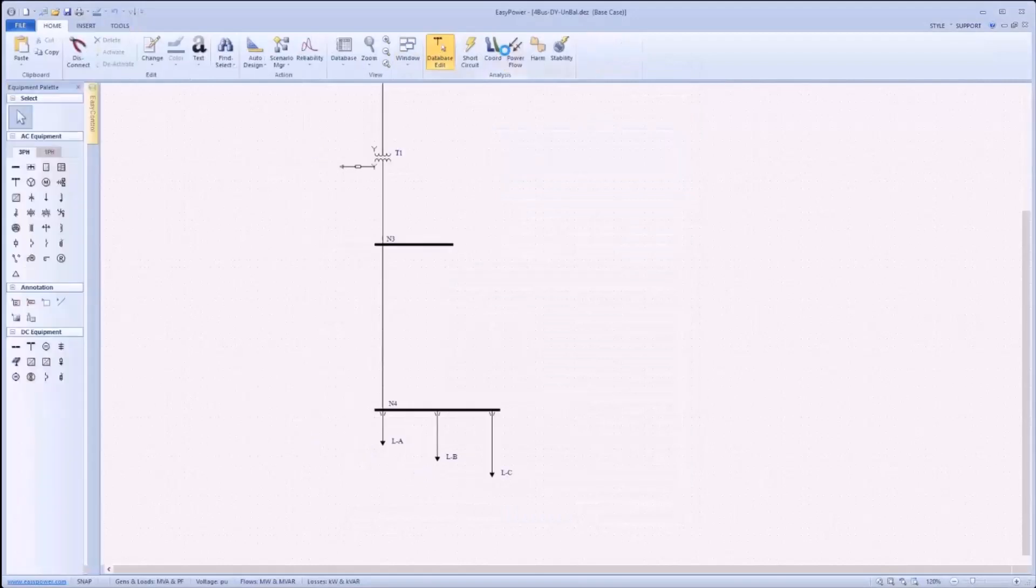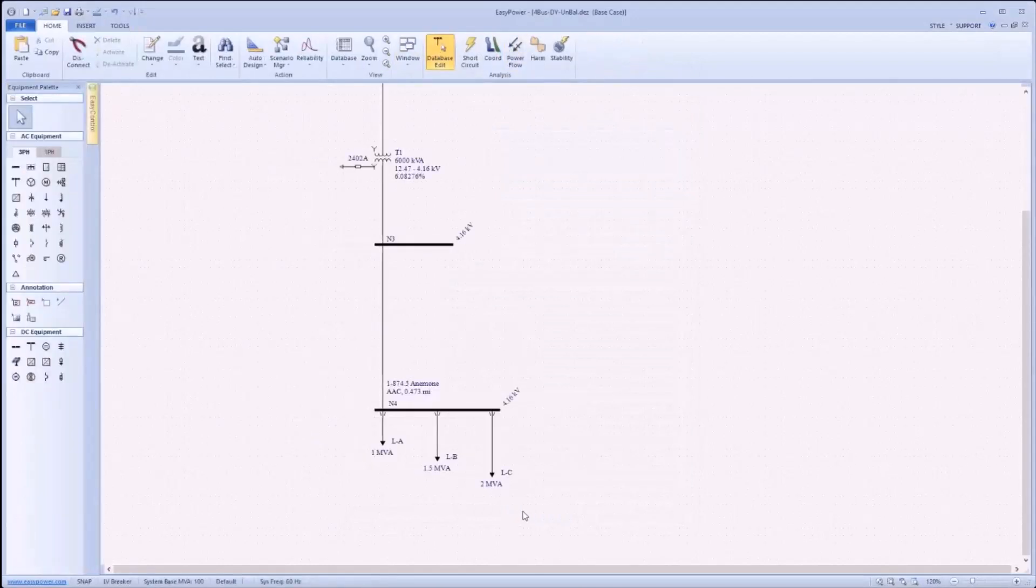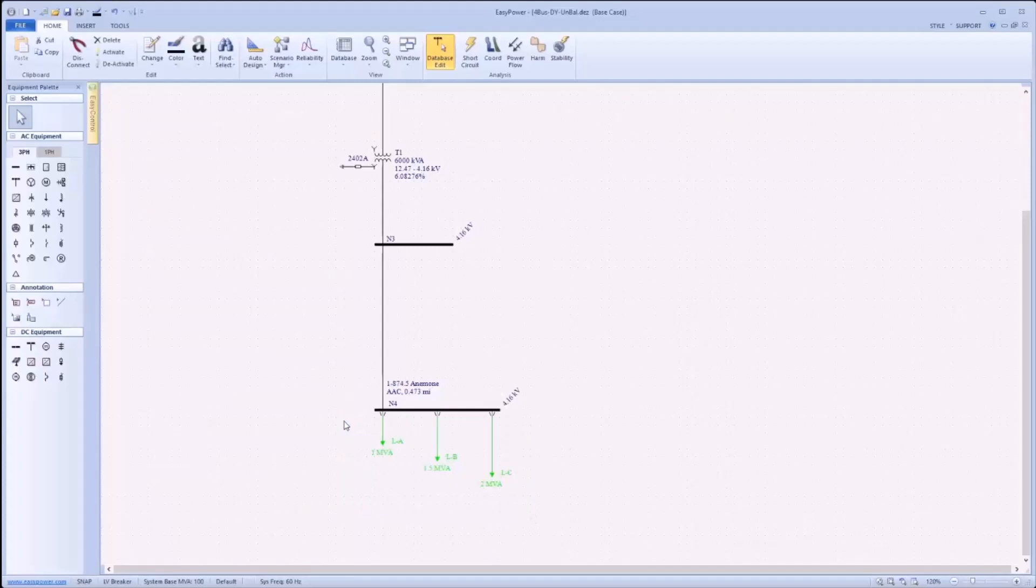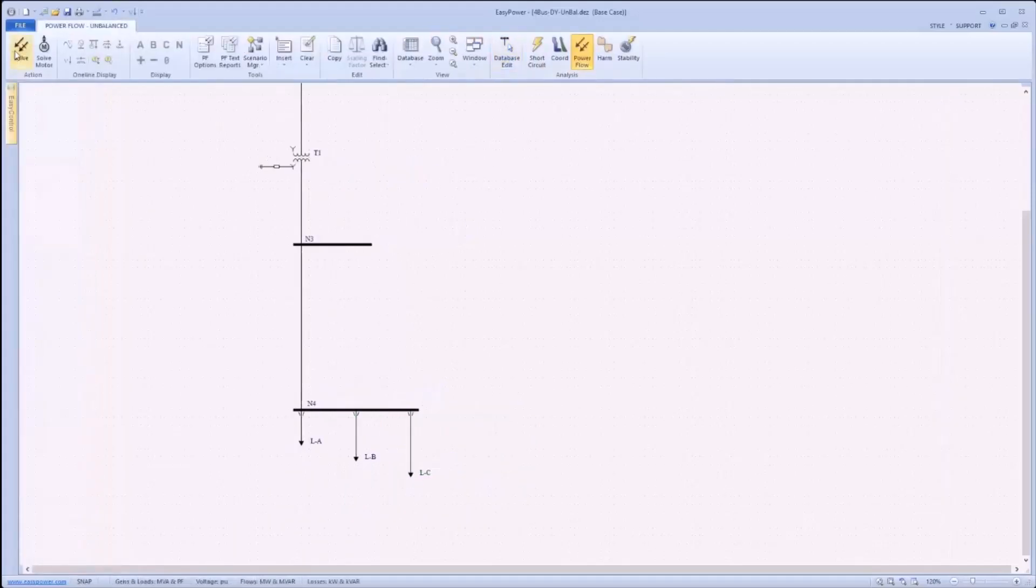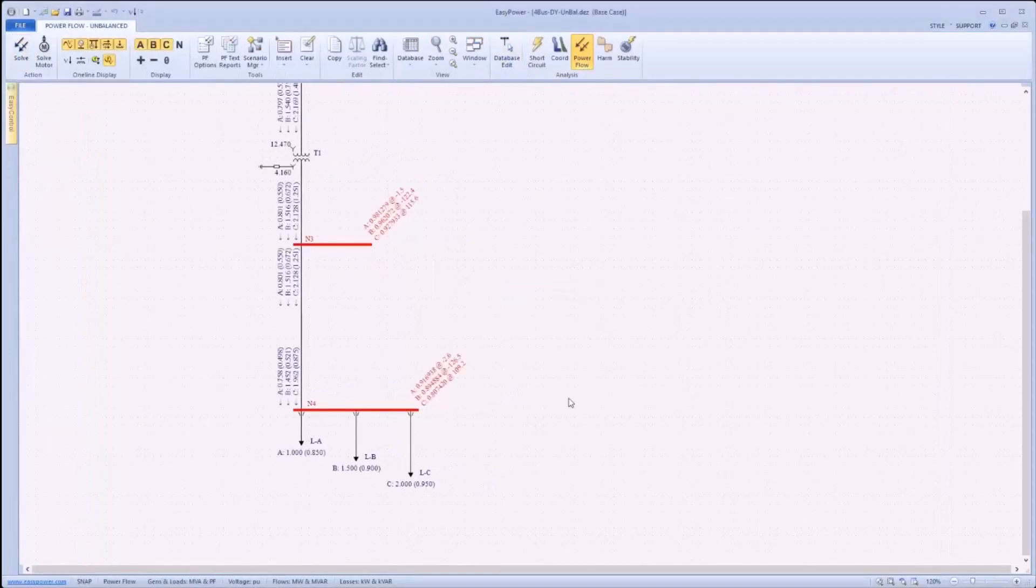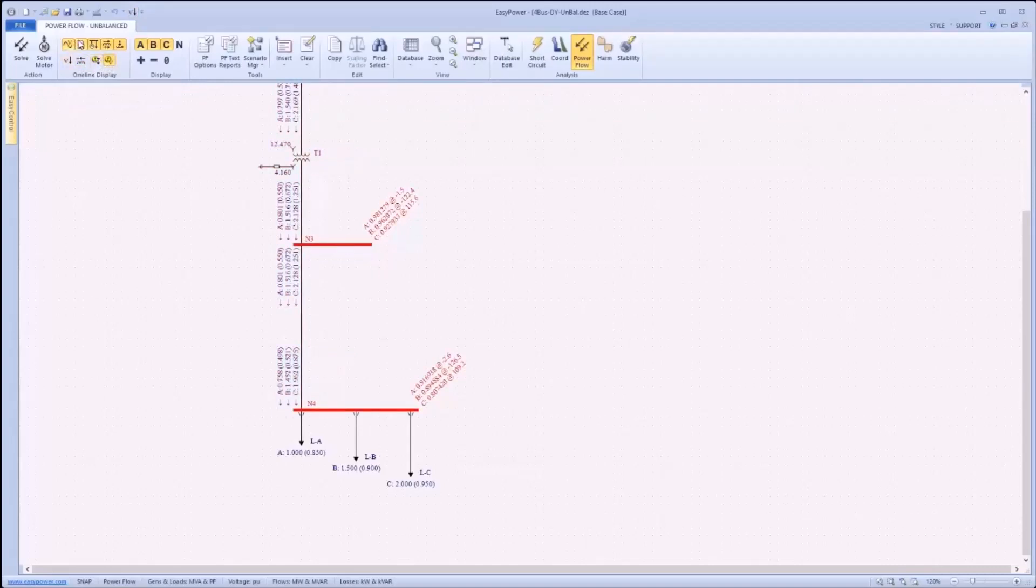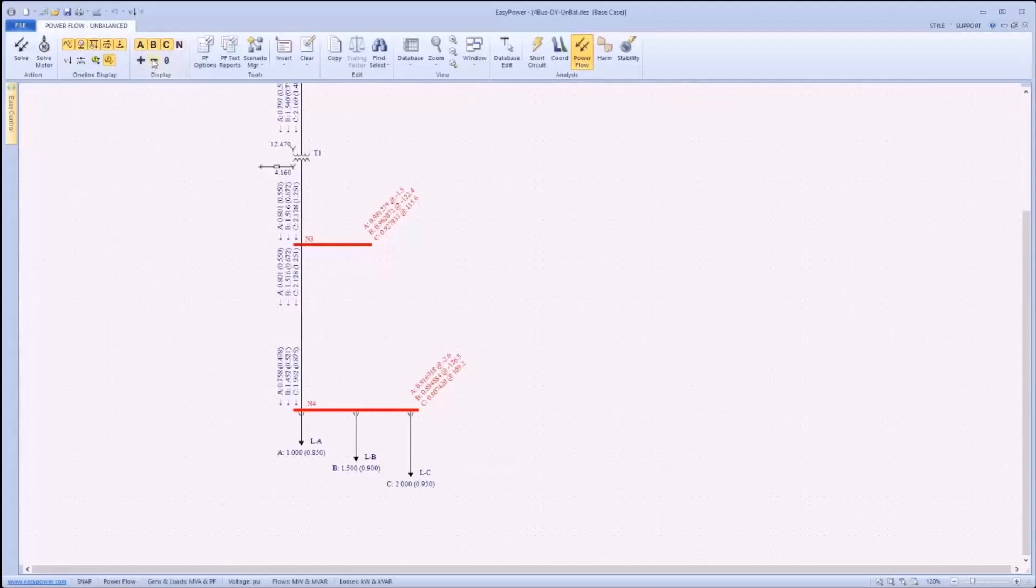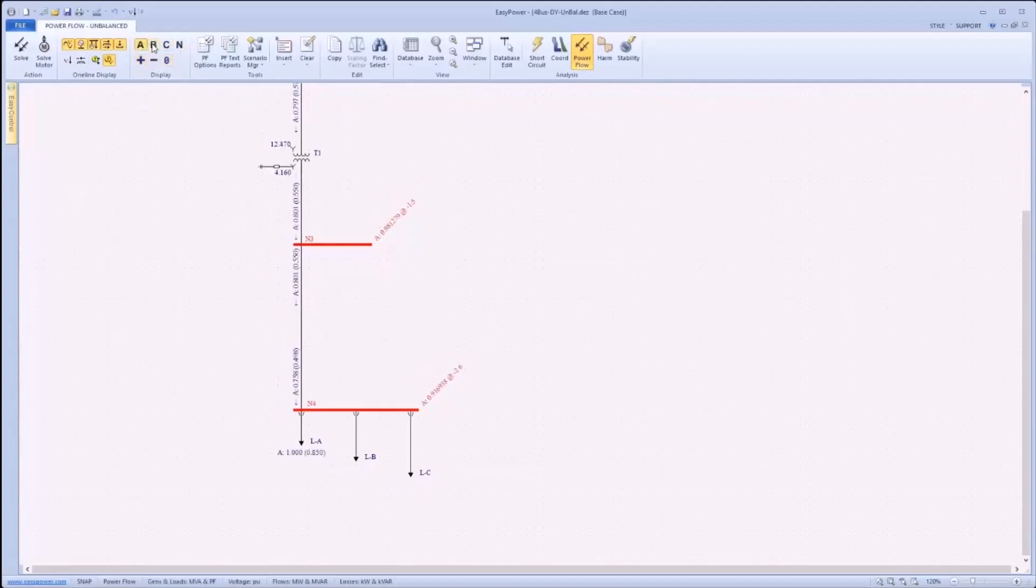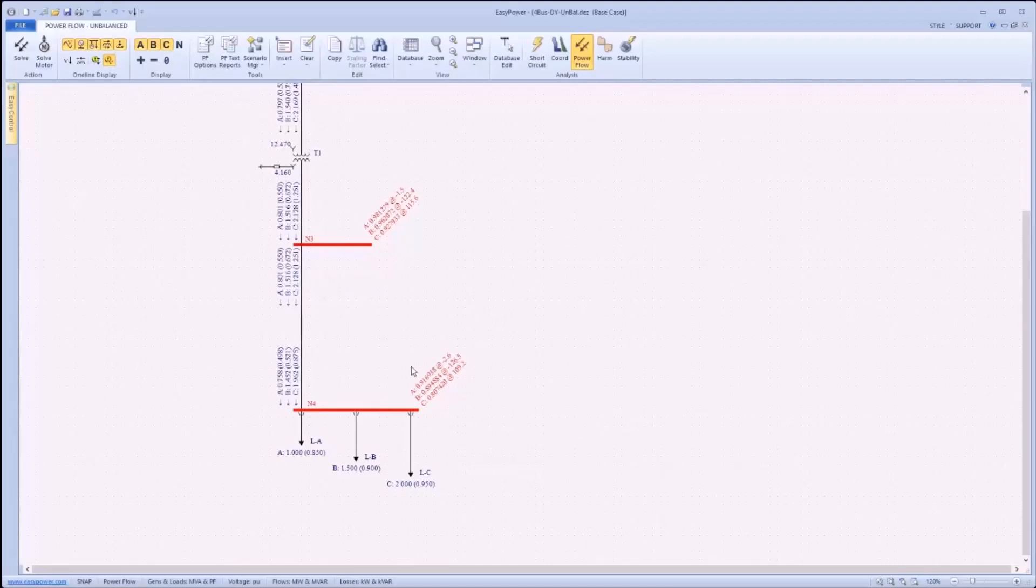Navigating back to Database Edit View, it can be seen that this system contains three single-phase loads, unbalanced, connected to bus N4. To solve the power flow, simply navigate back to power flow and click on Solve. There are one-line display options that can be selected for voltage drop, losses, overloads, voltage violations. In addition, standard options for the one-line display listed above. As well as those one-line display options, users can select from A, B, C, N quantities or positive, negative, and zero sequence quantities. In this case, note that the branch flows and bus voltages being shown for individual phases are unbalanced. Each phase has different quantities displayed as is expected due to the unbalanced loading present at bus N4. Both bus N3 and N4 have been flagged for voltage violations here based on the various settings specified in the control menu of power flow options that was just shown.